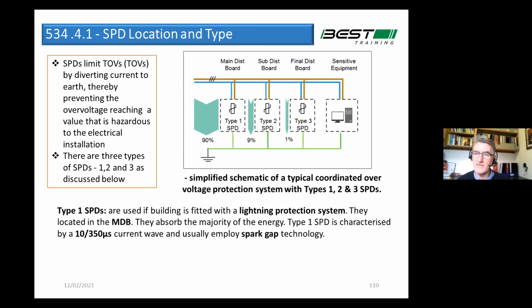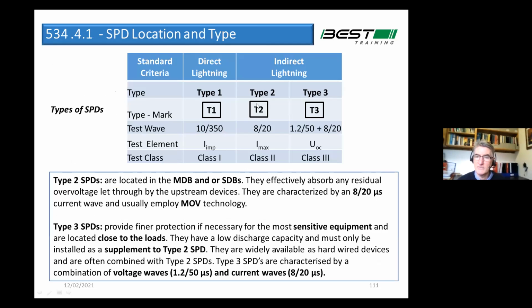It literally sets up very, very high voltages, and when I say burn, it'll burn out things like integrated circuits in your television or whatever. So that's why we use these systems. Type 1, if you have lightning protection. Otherwise, your main SPD is a type 2, and then you use either type 2, combined type 2 and 3, or type 3 downstream, etc. Ultimately what you're trying to do is protect sensitive equipment, like your PC and TV, against voltages, as these are only designed to withstand impulses up to 1.5 kV. So what you're trying to do is clip the voltage and make sure you don't get voltages of that level appearing throughout your installation. And they are type 1, type 2, and type 3.